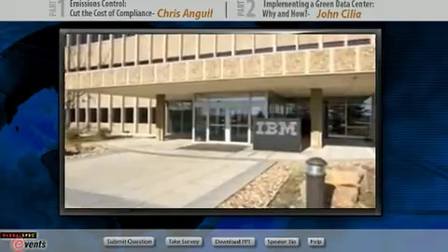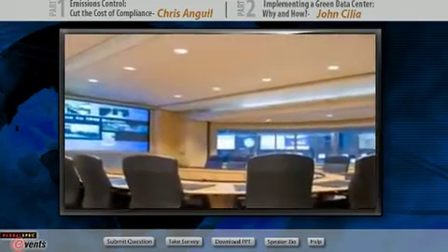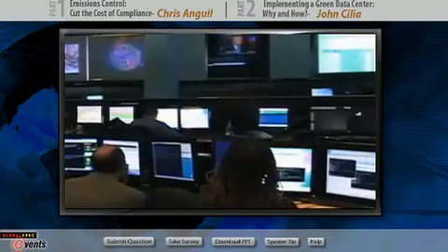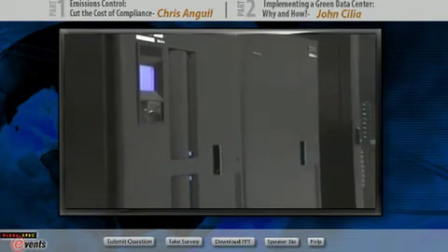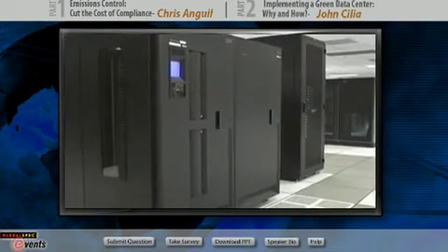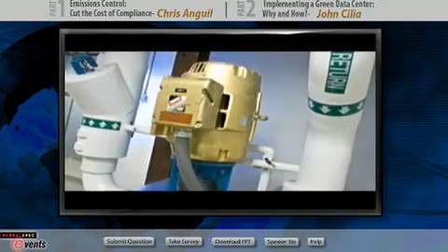Pursuit. GDC construction and operation involves a variety of advanced technologies and strategies. For example, first, one must build an inventory that includes IT systems, all mechanical and electrical equipment, as well as supporting infrastructure. Operating data must then be gathered and analyzed to determine how much energy each piece of equipment is using. Once this baseline is established, proposed implementation strategies must factor in new requirements and growth estimates. Simply replacing older, inefficient equipment will not get the job done. In fact, this approach could adversely affect existing data centers due to insufficient power and cooling capacities.